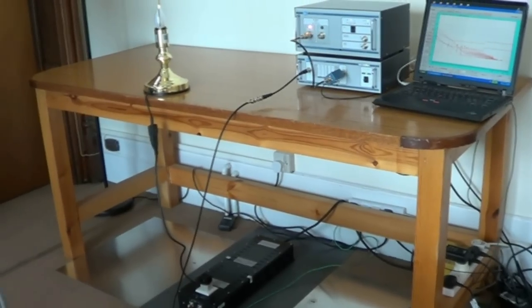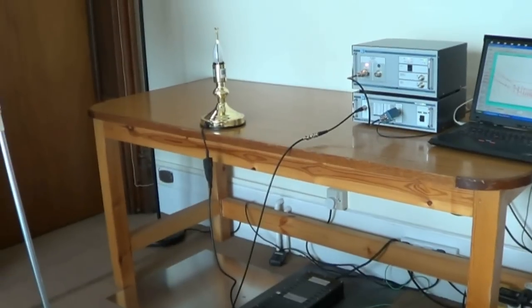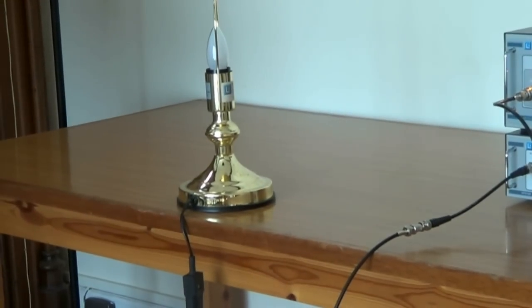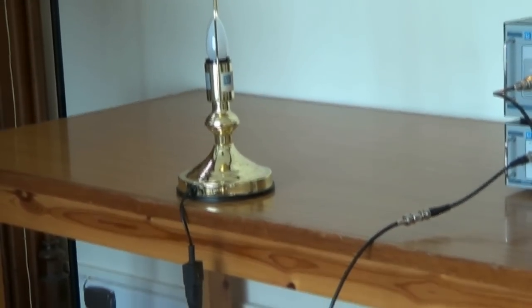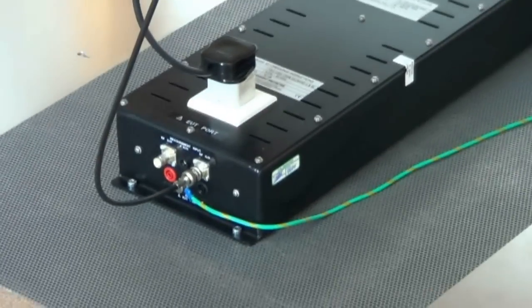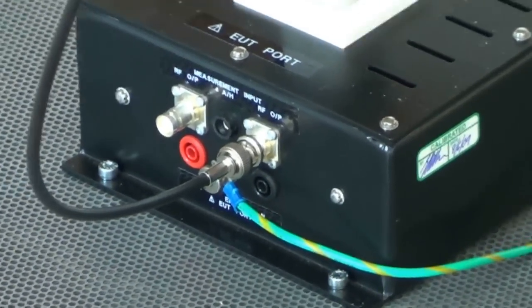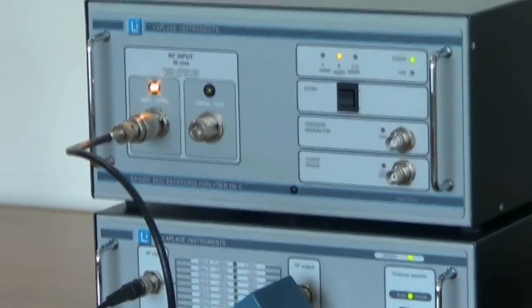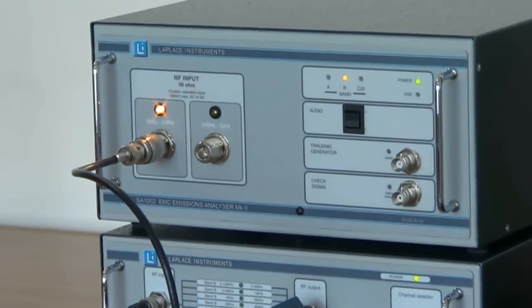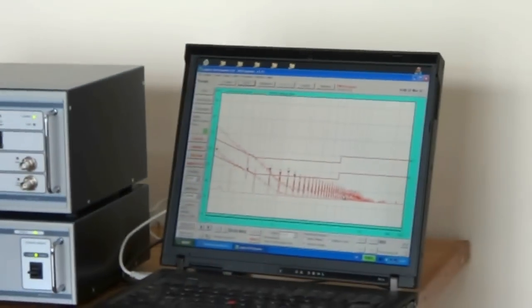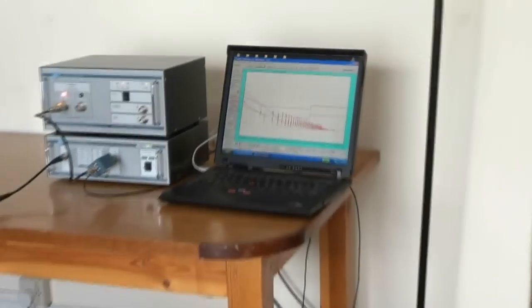So here is our test setup. Our product in this case is a table lamp, so this is our EUT. This is wired to an LISN which is bolted down to the ground plane. And the output from the LISN goes to our pre-selector, and from there it goes up to our analyzer. And the analyzer in turn is connected to our PC.